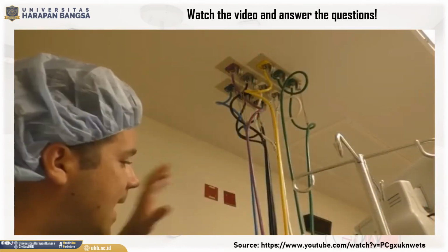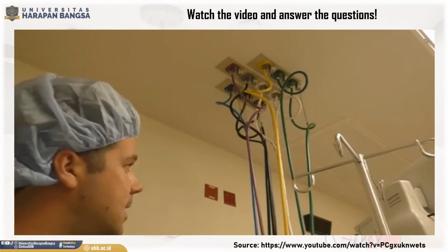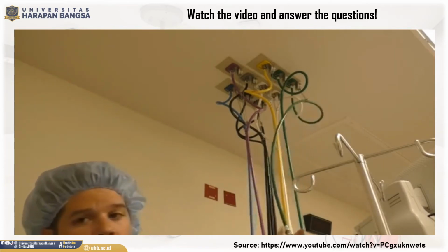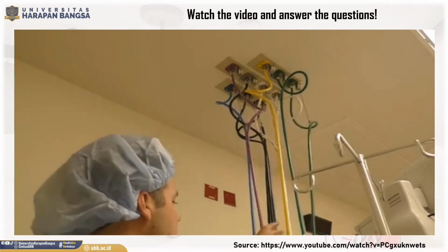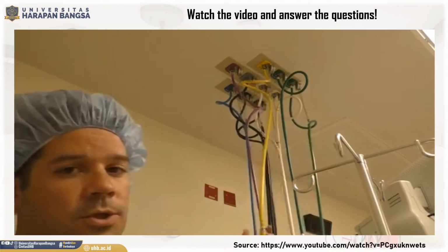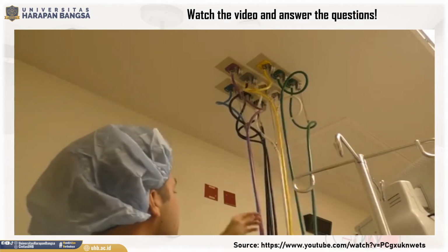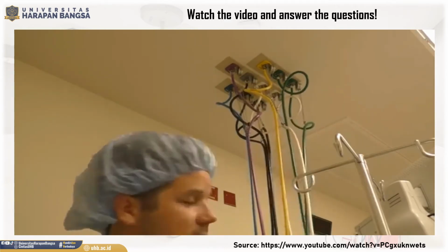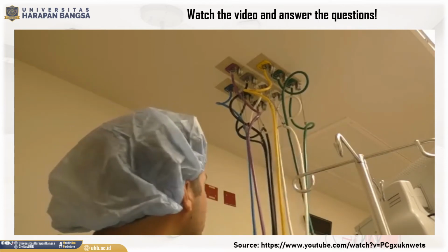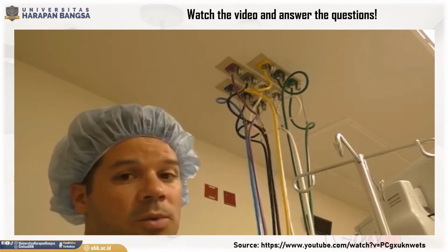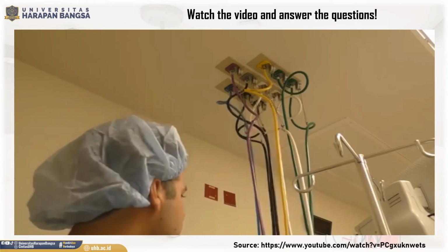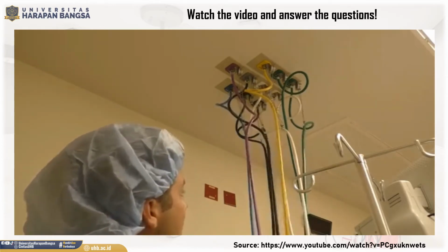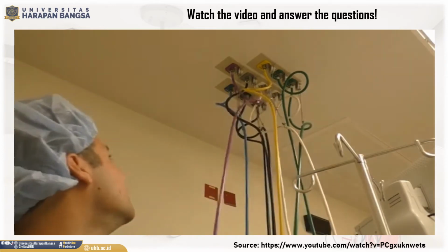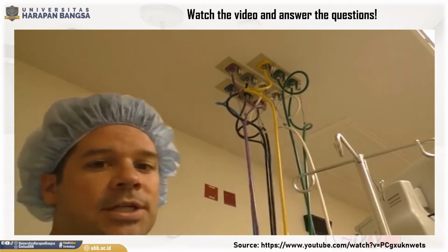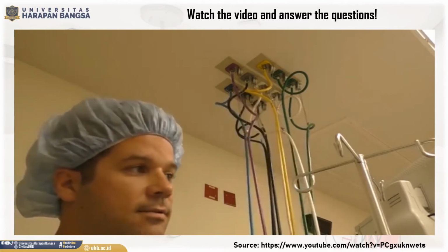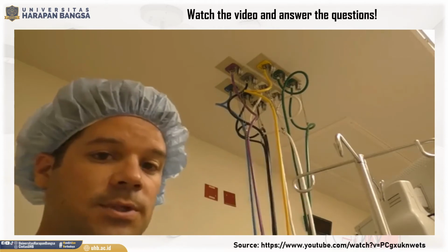So as far as gases that are hooked directly up to this anesthesia machine, we have green, which is oxygen. We have yellow, which is just medical air. We have white, which is basically just a medical vacuum line. We have blue, which is nitrous oxide. And then we have purple, which is labeled WAGD, and that actually stands for waste gas disposal system.